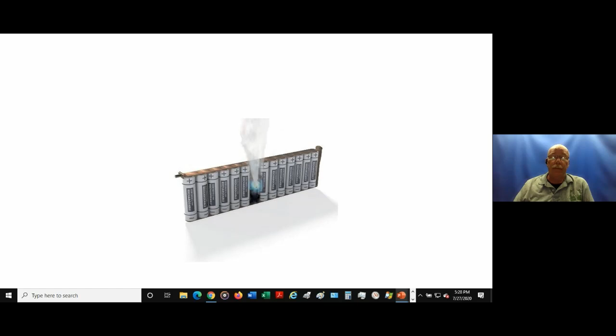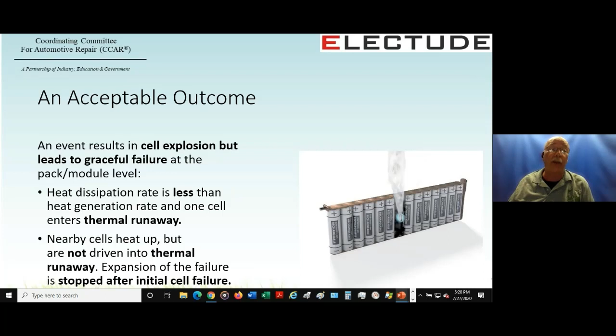So to recap, failure occurs within the cell that leads to an increase in temperature from overcharge. Reaction within the cell creates additional heat and gas and the reaction zone expands. Heat dissipation rate is less than the heat generation rate and the cell enters thermal runaway. Additional heat and gas are produced, the cell vents and explodes. Nearby cells heat up but are not driven to thermal runaway, and the expansion is stopped at the initial cell, which brings us to the acceptable outcome.